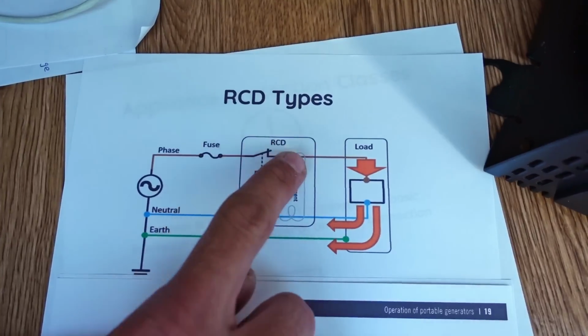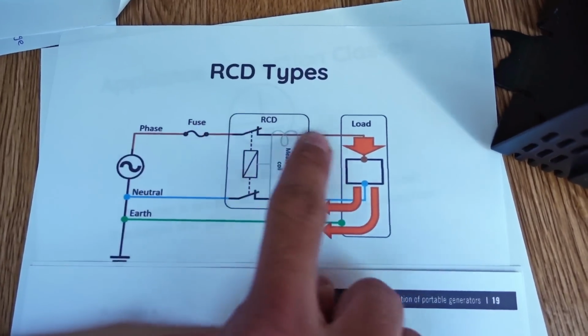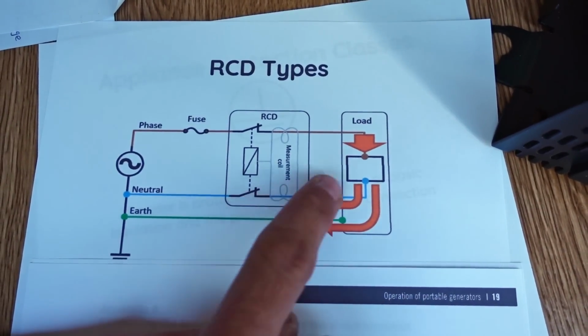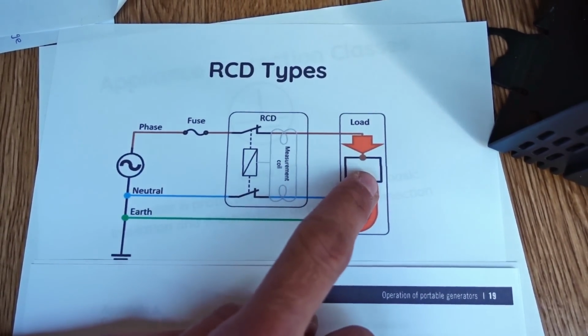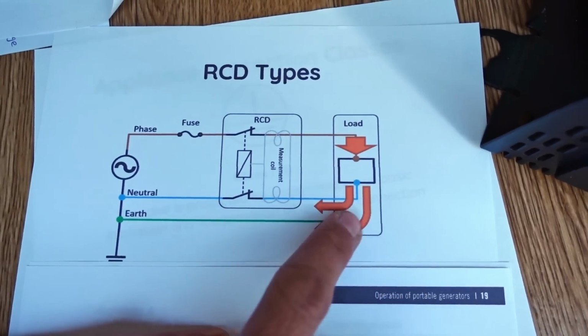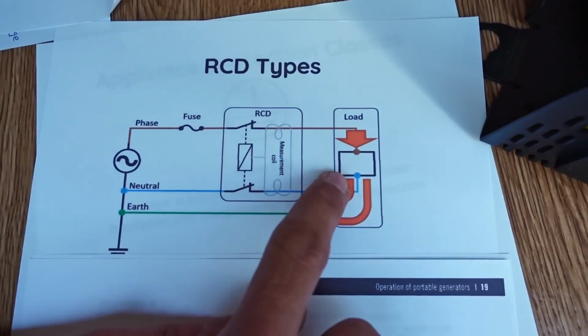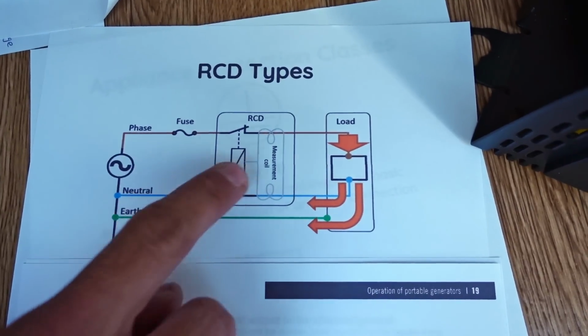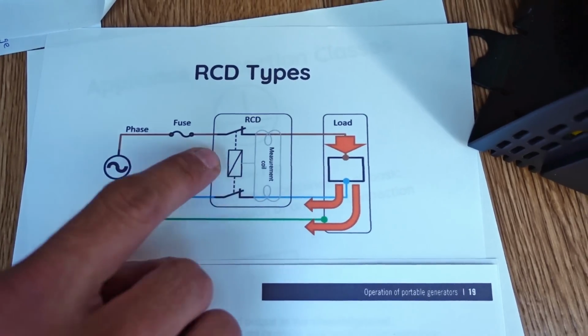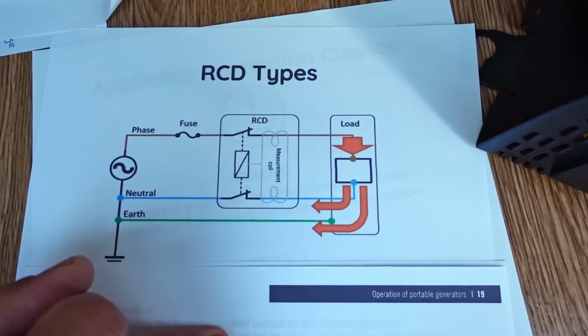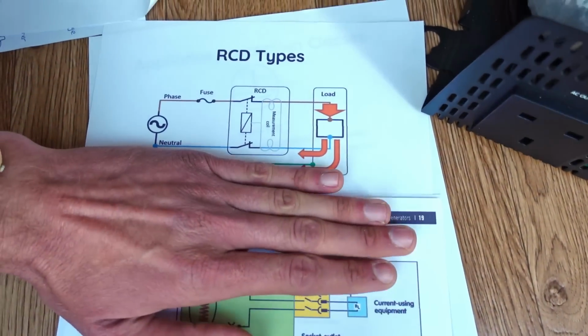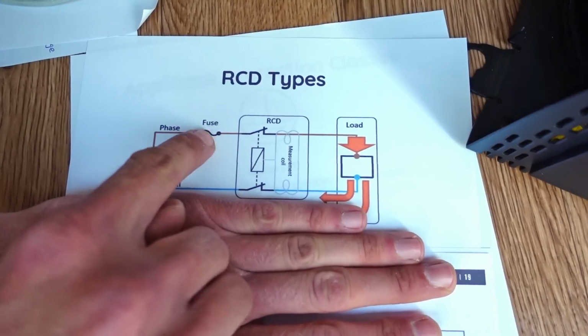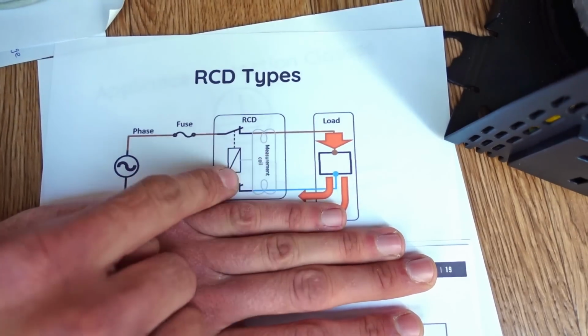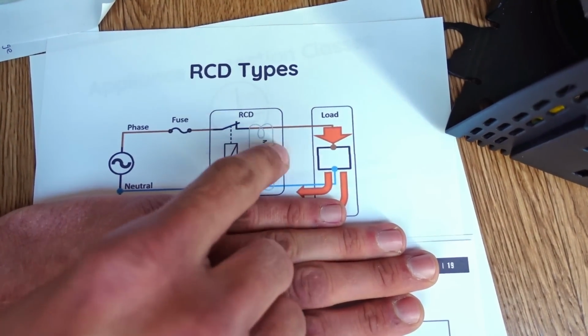If ever there's a situation where the current going out on the live differs from what's coming back, for example if a device is faulty, some current might go back through the earth wire instead of the neutral. An RCD is very sensitive and will trip straight away to cut the power. But without an earth wire, it can't work, because the only way for current to get back to the source is via the neutral wire, so the RCD in that situation won't do anything, it's completely useless.